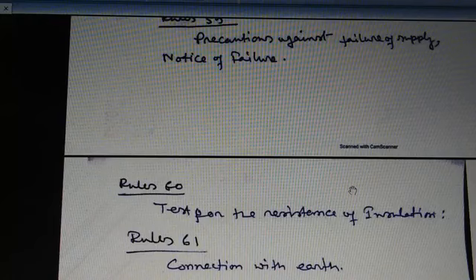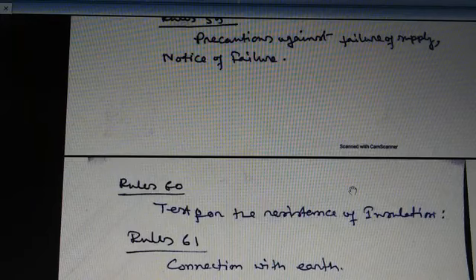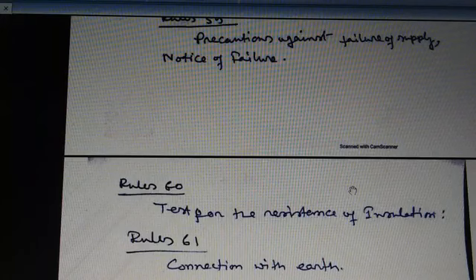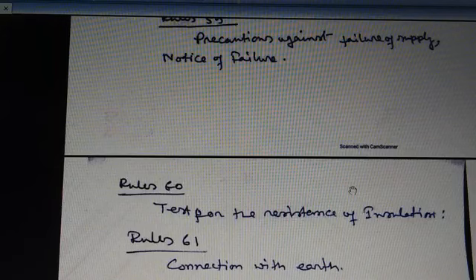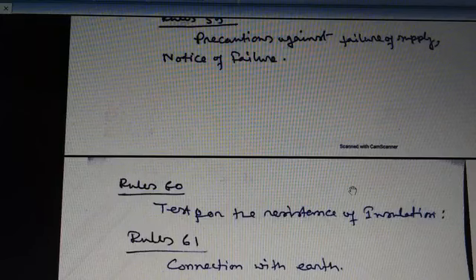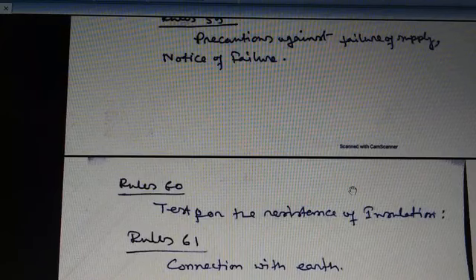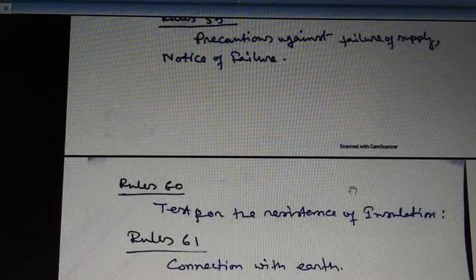During the reading period, if the pointer is placed at infinity, then we can consider that the insulation resistance of this particular insulator is infinity. So we can consider the insulation is good and the resistance of the insulation is very good. If the pointer shifts from infinity toward 0 during the measurement period, then we can consider the resistance of the insulation is very poor. So this insulation is not safe for working purposes.